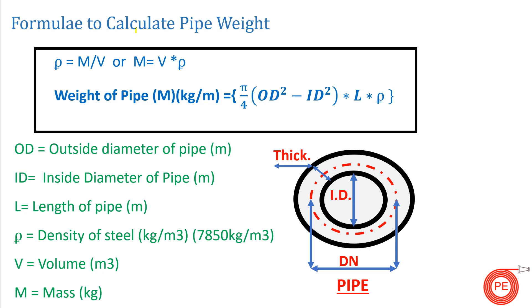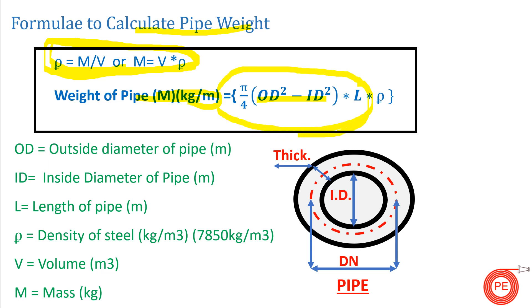The formula to calculate pipe weight uses the basic principle: density equals mass divided by volume. The weight of the pipe in kg per meter is given by (π/4) × (OD² − ID²) × L × ρ. The term (π/4) × (OD² − ID²) × L represents the volume of the pipe, treating the pipe as a hollow cylinder where L is the length.